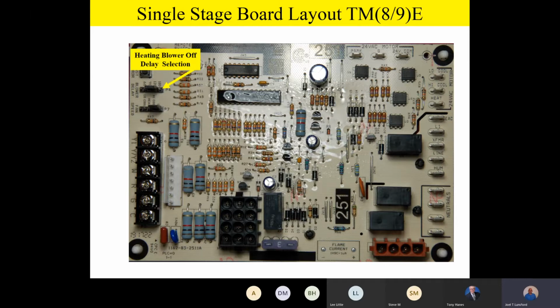This is a heating off delay jumper, and it goes all the way from 60 to 180 seconds. Now, we typically set it up at 90 to 120 seconds, about in between from the factory. But you've got that field selectable capability of changing from 60 to 180 second off delay when the call for heat goes away. So that's pretty nice from a comfort standpoint. If the homeowner's complaining that they love our furnace, but it kind of blows cold air after a couple minutes, well, you can take that down to 60 seconds or 90 seconds if you want to help improve that comfort complaint. If you're getting like a cold blow complaint at the conclusion of your heating cycle.